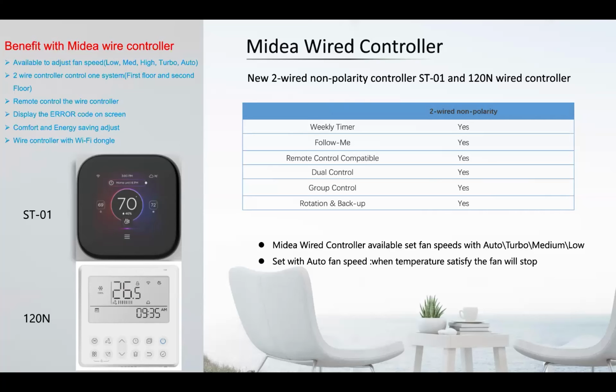It's capable of group control, which means you can control more than one unit with one control. And then it also has rotation and backup. So you can have 2 units. You can set by address, you can set one to run at this time and another one to run at this time. On the left, you will have fan speed control. You will have low, medium, high, turbo, and auto.